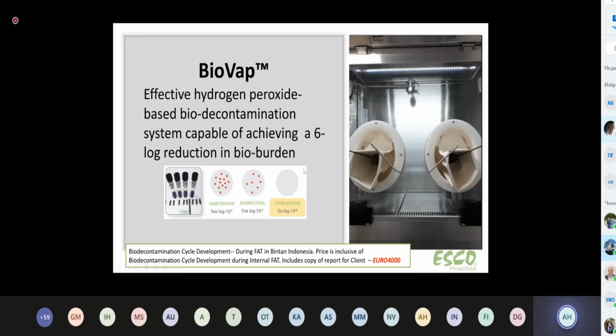Okay. So BioVap actually is allowing you to achieve a sterilization of 6 logs reduction, 10 to the power of -6. So if you actually use a wiping with alcohol, with a wipe, you wipe, maybe you can achieve 2 log or sometimes even 3 log reduction, not more. Now, there are many other liquids that are actually going to be used in biosafety cabinets, like sodium hypochlorite. What else? Quaternary ammonium. All of this actually is good, but for isolators, we use hydrogen peroxide.